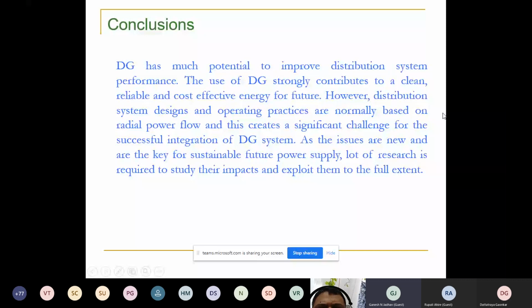Some of our colleagues have experienced this: they installed a solar PV at the petrol pump. When the petrol pump is connected with the grid, there is no problem of the reference frequency. But when the electricity is gone, as the reference frequency is not available, that inverter was not going to work continuously. So to track the frequency under off-grid mode, that is the main issue. How to give the reference frequency in the inverter, because nowadays in India, whatever inverters are coming, we are not able to set the frequency in that. So how can we work on that?